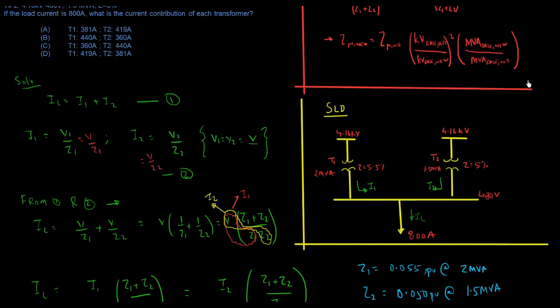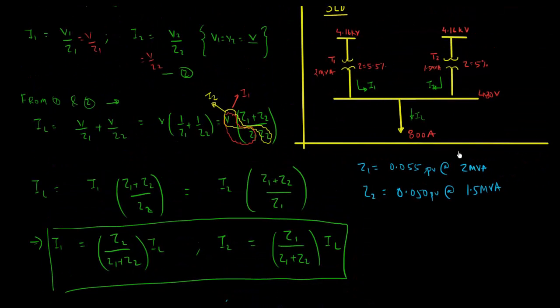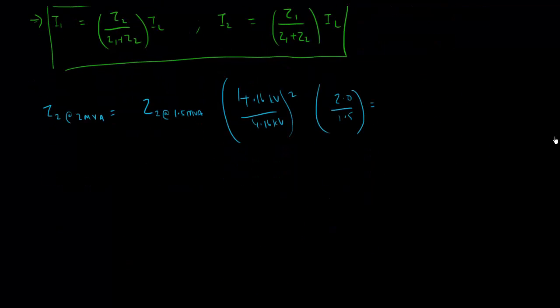Converting Z2 to the 2 MVA base: Z2' = 0.05 × (2/1.5). Plugging this into the calculator gives Z2' = 0.067 per unit. Now we can use this converted value — call it Z2 prime — in our formula, substituting it in place of the original Z2.